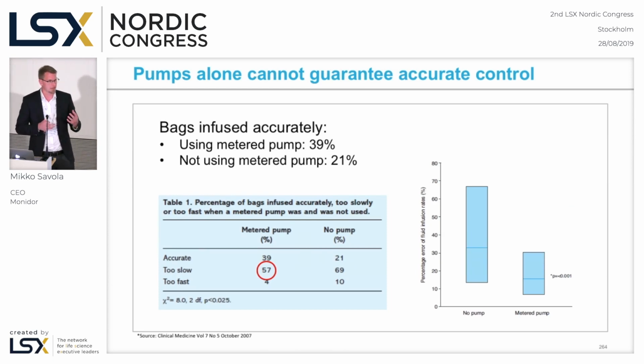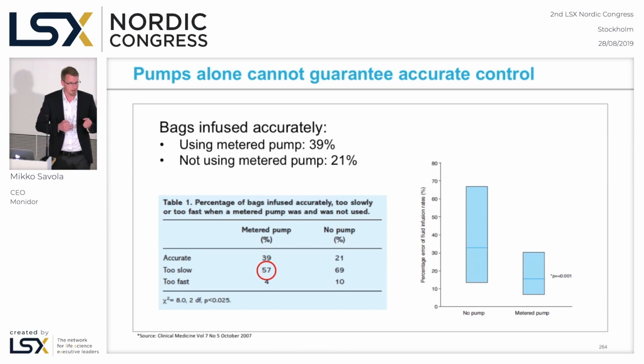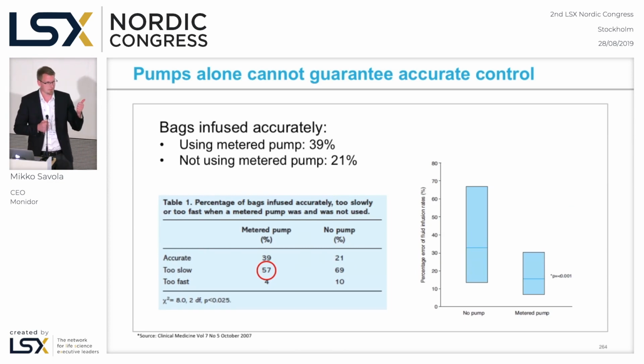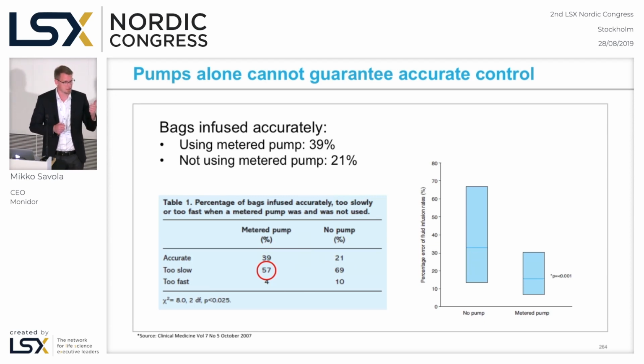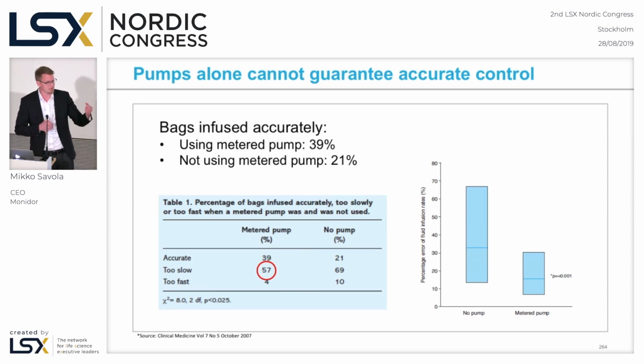Additionally, pumps alone cannot guarantee accurate infusion therapy. This research shows results when infusions were given manually, and 21% of the bags were infused accurately. When a pump was used, only 39% was infused accurately. It's a great improvement, but cannot solve the problem. And it was assumed in this research that more effort should be put on checking infusion, even though pumps were used, because they are alarming and need some control after alarm.